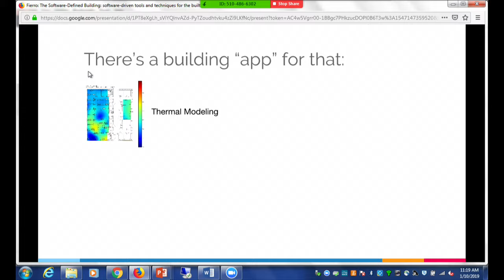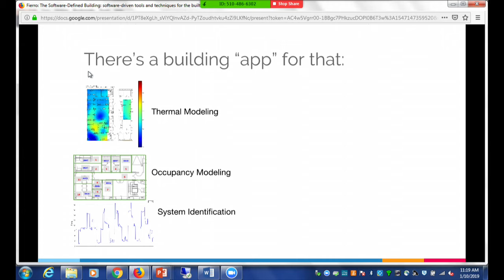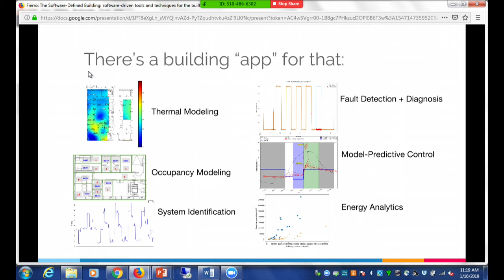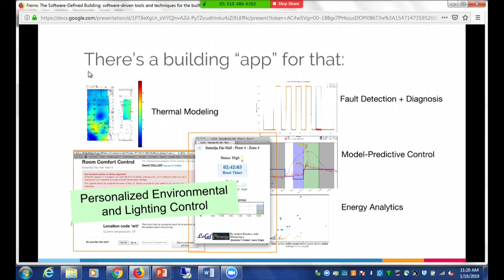Occupancy modeling: how do I infer when people are going to be here and when they go home, without asking everyone to sign in and out? What information in the building can I leverage to infer that through data? System identification: how much energy does my equipment use? Fault detection and diagnosis: did my damper break? Model predictive control: how do I design an optimal control algorithm to meet some bounds? Energy analytics: what's my energy use per square meter in this building? Personalized environmental control, demand controlled ventilation, microzones, thermal comfort.